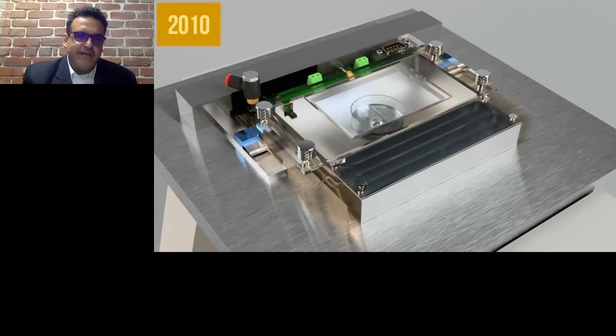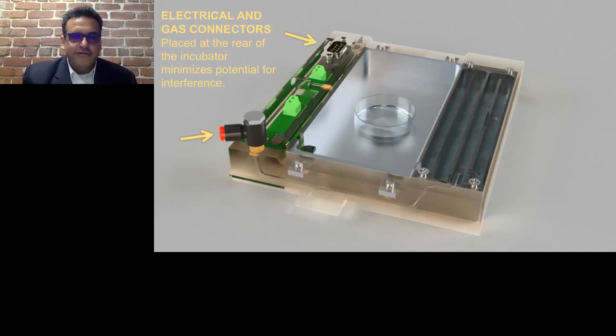It really closely parallels the designs of commercially available incubators. Some of the features that I was able to bring in because of 3D printing are these manifolds. Highlighted in green there is a little tube that's printed as part of the housing. That's one of the nice capabilities that 3D printing gives us, the ability to print these kinds of long passageways inside of parts. It used a metal aluminum tub to provide some thermal stability and distribute the heat around. And there were two Kapton thin film heaters attached to the underside of that aluminum block, and that's what heated up the sample chamber.